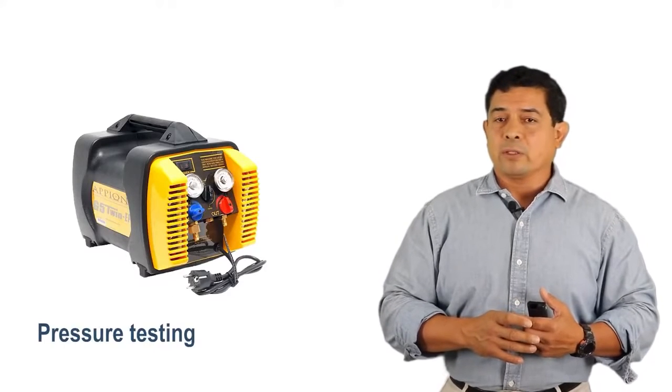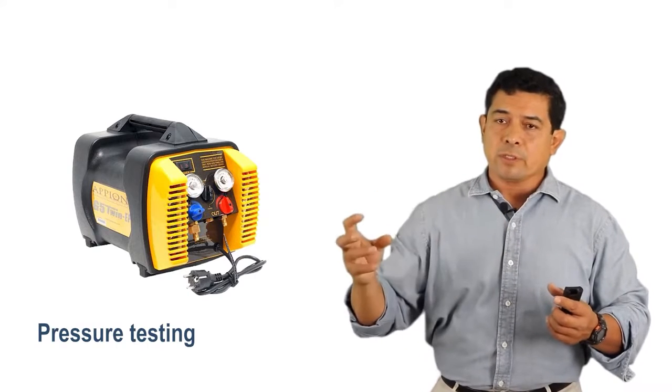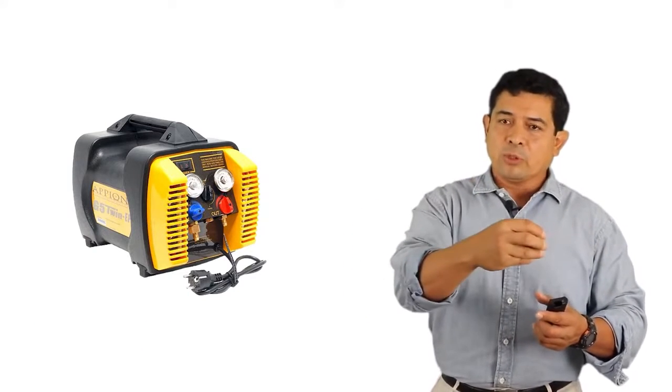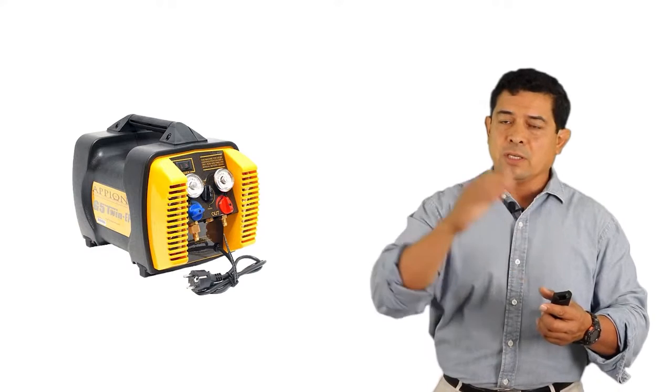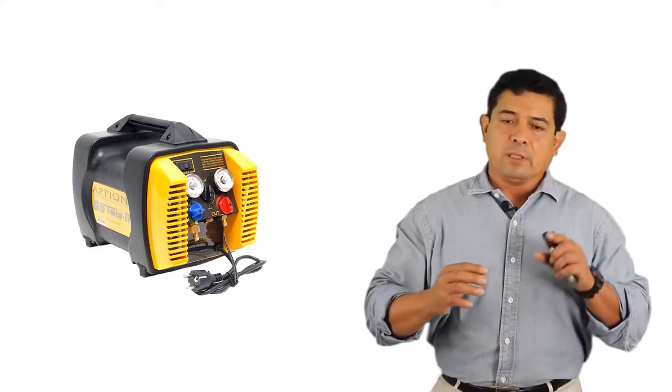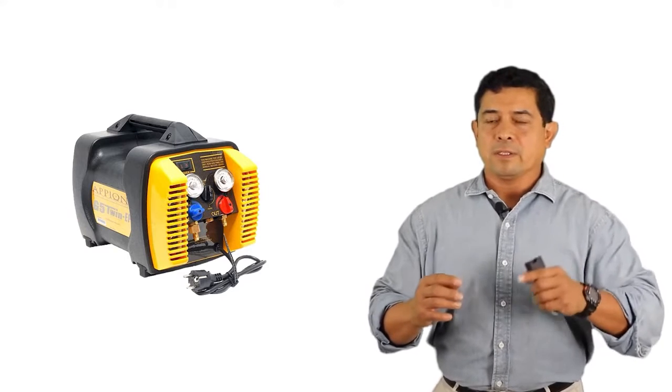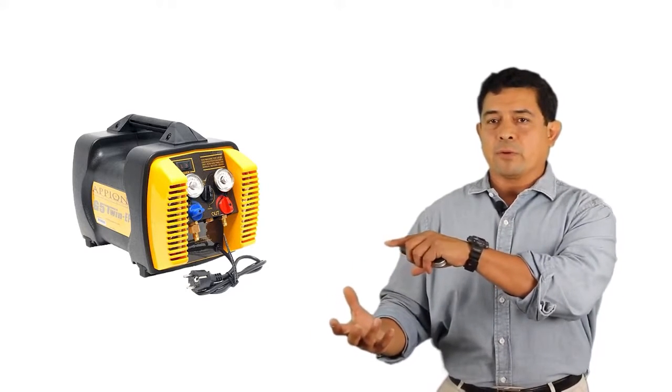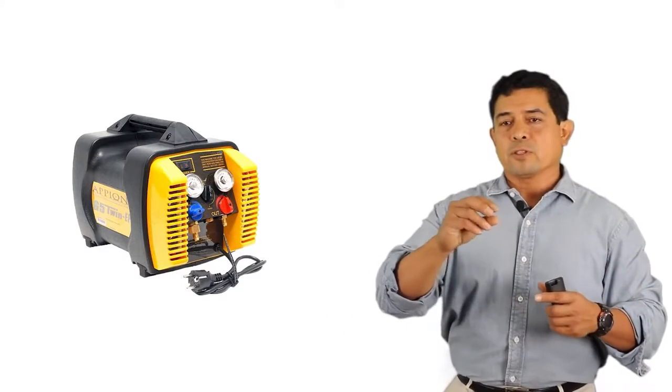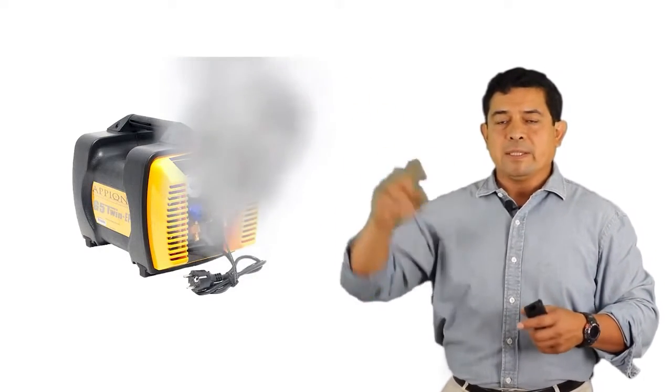You have to check the recovery equipment for refrigerant leaks on a regular basis. If you're pulling a vacuum on the system with a recovery machine to get it down to proper levels and you don't check for leaks, you may introduce air into the system and contaminate the recovered refrigerant. If refrigerant is coming out and you have a leak, you're going to be releasing refrigerant to the atmosphere. So check for leaks so that you do not introduce air into the system or leak refrigerant out.